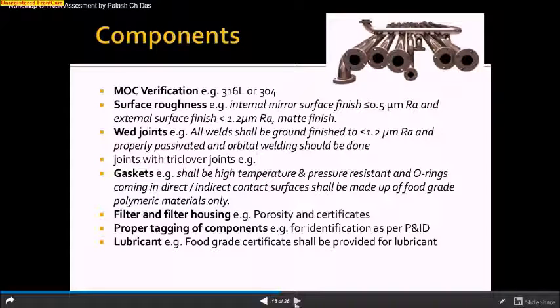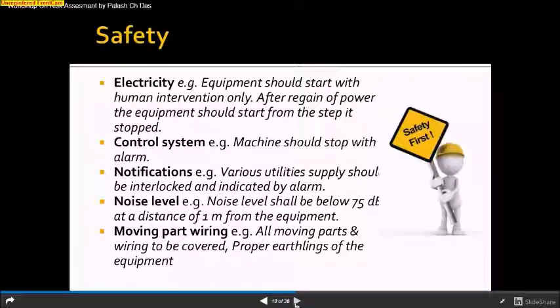So the first point is electricity. Equipment should start with human intervention only. After the power is regained, the equipment should start from the step where it stopped. As you know, it is process safety, and it is personal safety also, for those who are working on the floor. Control system, machines should stop with an alarm so people can identify that yes, it is stopped. Notification, various utility supplies should be interlocked and indicated with an alarm.